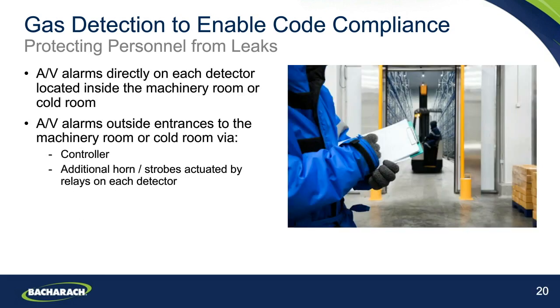It can be very useful to look for audio-visual alarms being directly on each detector inside of the machinery room or the cold room. This really comes down to a case of convenience and simplicity of installation of a system. It really cuts down on the hardware and installation requirements from having to install additional devices for each audio-visual alarm that is required. But of course, you do need to be able to drive those AV alarms outside the entrances to the machinery room or the cold room.